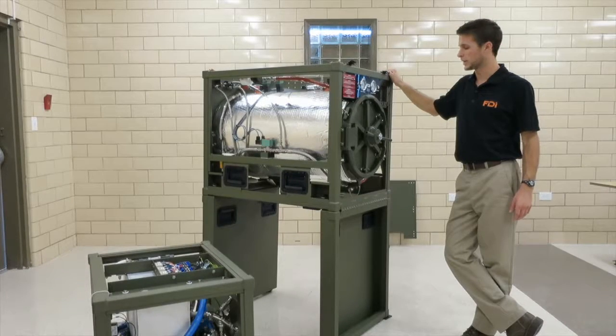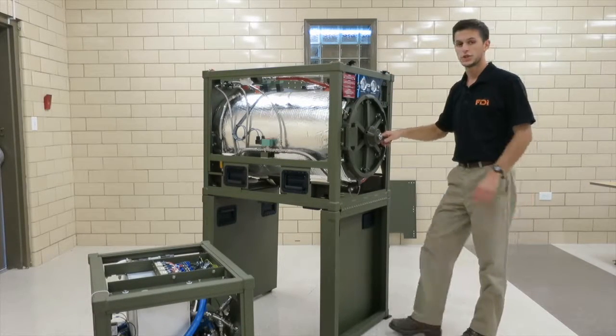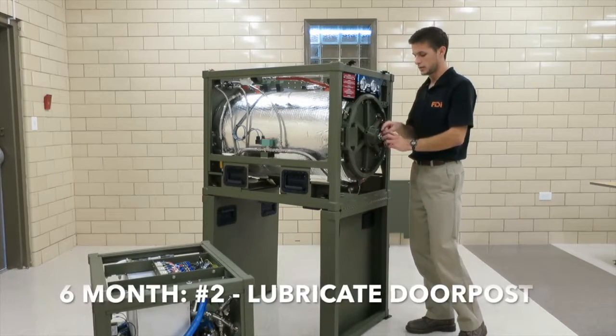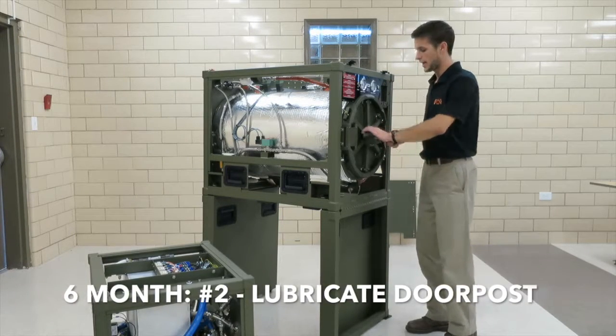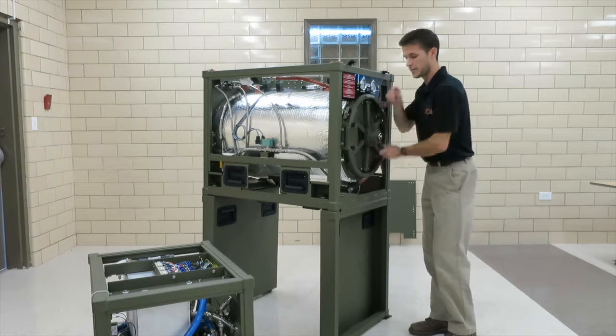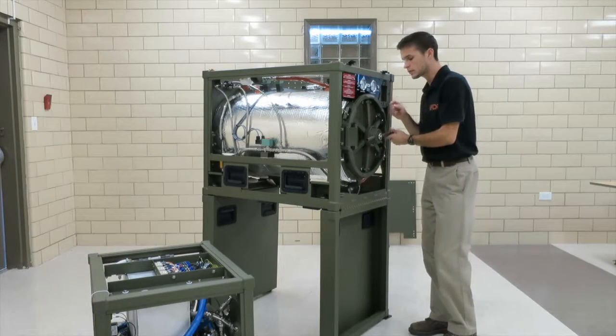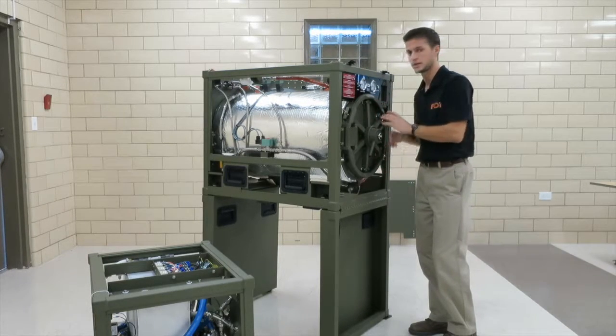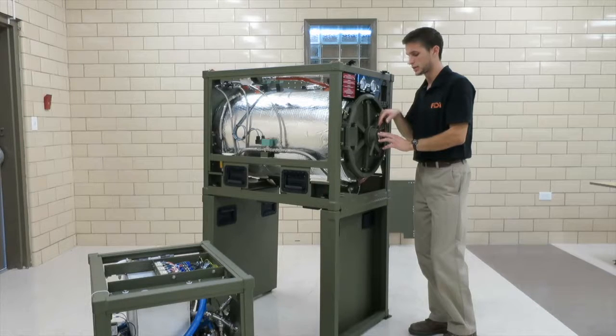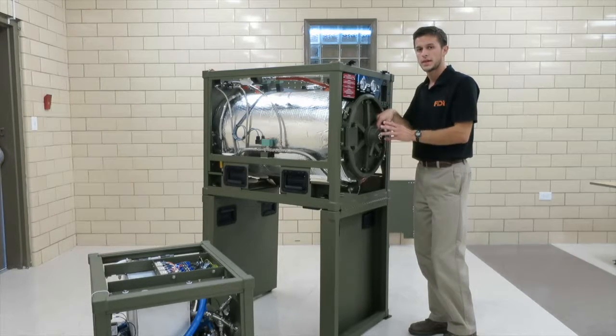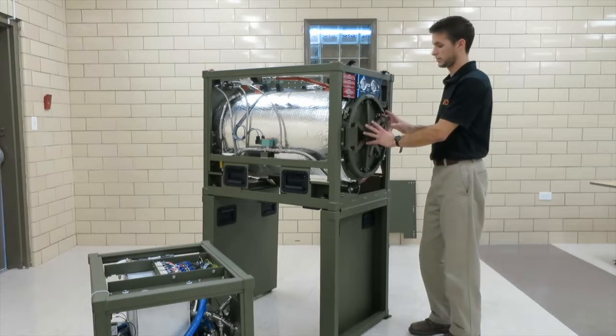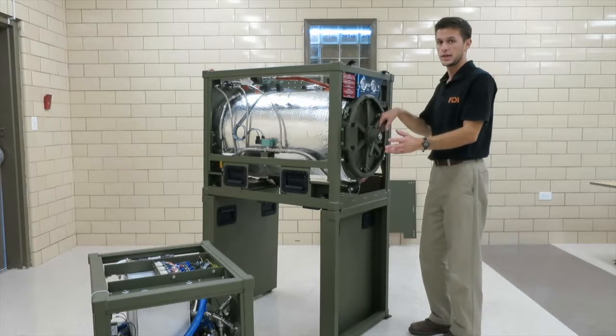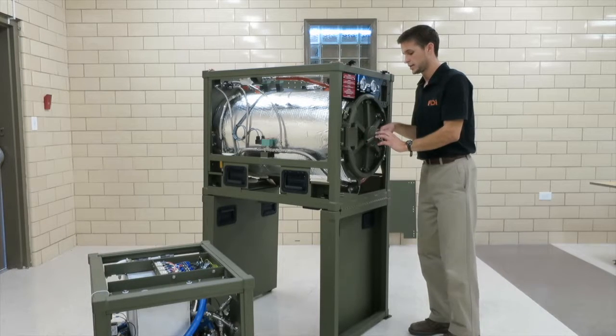All right, so the next one on the list is to lube the chamber doorpost. This is the doorpost right here, and this hub spins back and forth on it. So you're going to want to keep that lubed up every 6 months. Just a light touch of grease will do. NLGI number 2 is good. High temp, because this door and the doorpost get up to 273 degrees during cycles.